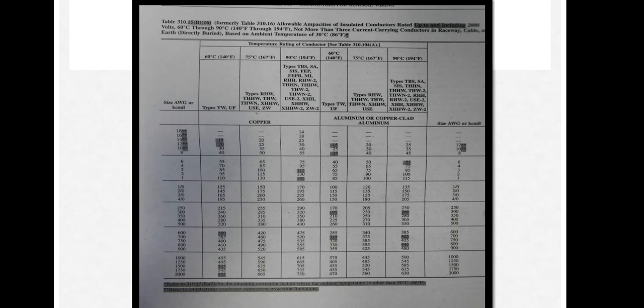Now, ampacities are derived from this table, Table 310.15(B)(16), and it's very important to read tables when you see them in the codebook. This table is based on two important principles: there are only three current carrying conductors in the raceway when these ampacities were measured, and this is at 30 degrees Celsius. Notice that it is divided into copper and aluminum, and each column for each type of insulation has a temperature rating: 90 degrees, 75 degrees, and 60 degrees.